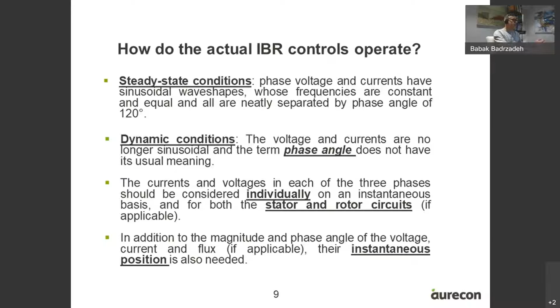What this means is that besides magnitude and phase angle, there is effectively a third dimension that needs to be taken into account: the instantaneous position of the current, voltage, or flux if there's an electrical machine. So the actual equipment needs the instantaneous position, in addition to magnitude and phase angle, to see what's happening in the external world, how it should respond, and how the control system should be designed and tuned. Let's go one layer deeper into the importance of this instantaneous position.